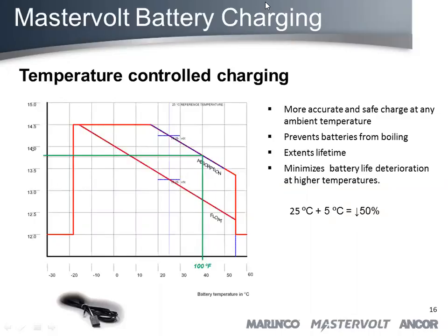Okay, so that's one thing. So in order to help that battery extend its life, we put temperature sensors on. What you see here, this is voltage, this is temperature. All the chargers are typically laid out at 25 degrees C. That's kind of an industry standard. That's that blue line that you see here. So this is your absorption voltage, and this is your float voltage. The absorption voltage is typically 14.25, that we just talked about earlier, and your float voltage is about 13.25.